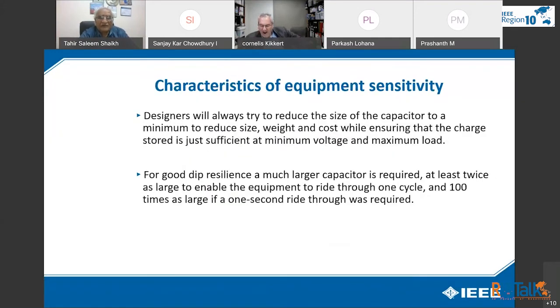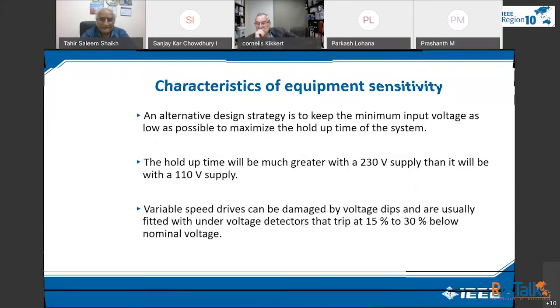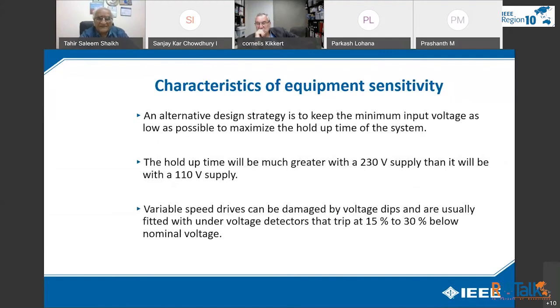Designers will always try to reduce the size of the capacitor to a minimum to reduce size, weight, and cost, by ensuring that the charge stored is just sufficient at minimum voltage and maximum load. For good dip resilience, a much larger capacitor is required, at least twice as large to enable the equipment to ride through one cycle, and 100 times as large if 1 second ride through is required. An alternative design strategy is to keep the minimum input voltage as low as possible to maximize the hold-up time of the system. The hold-up time will be much greater with a 230-volt supply than with a 110-volt supply.